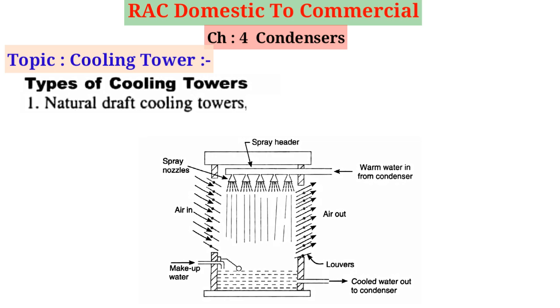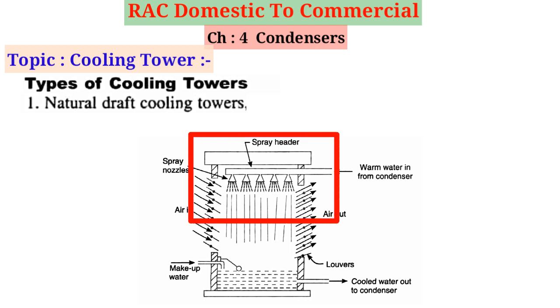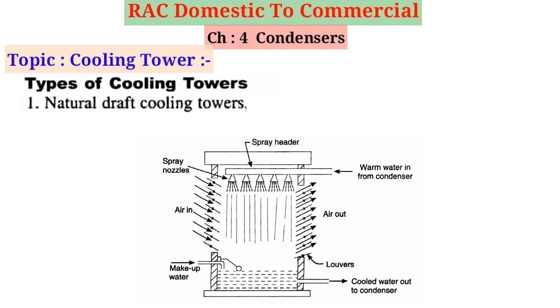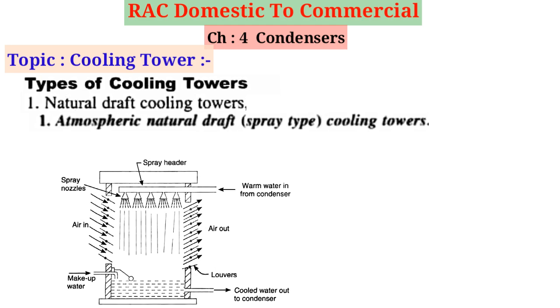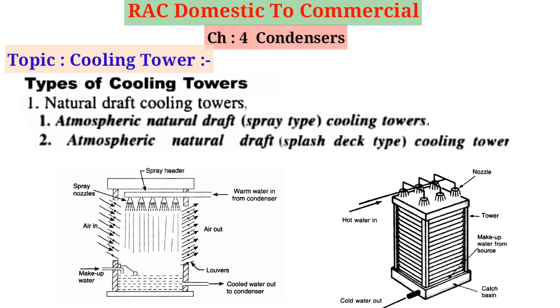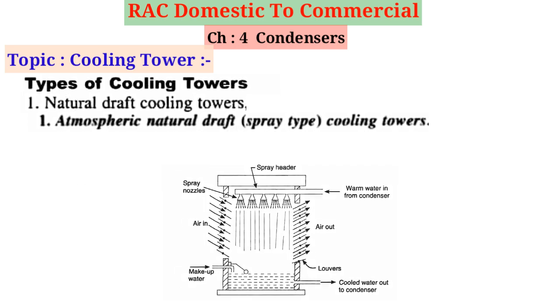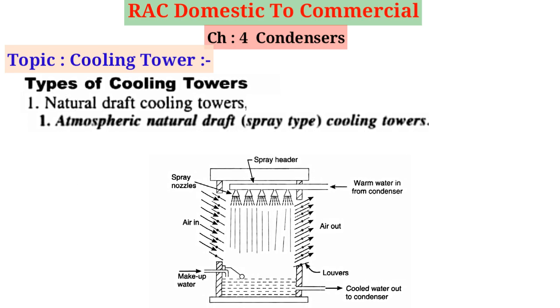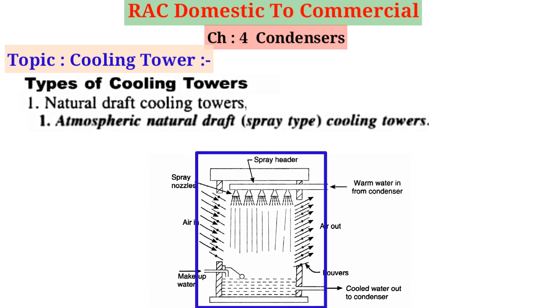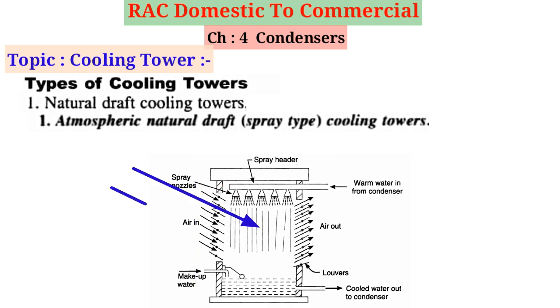Natural draft cooling towers are equipment where atmospheric air circulates and cools down the hot water of the condenser. These are divided further into two parts: Part 1 is the atmospheric natural draft spray type, and Part 2 is the atmospheric natural draft splash deck type. The atmospheric natural draft spray type cooling tower is a box-shaped structure with louvers. The louvers allow atmospheric air to pass through the tower but slant down towards the inside of the tower to retain water in it.